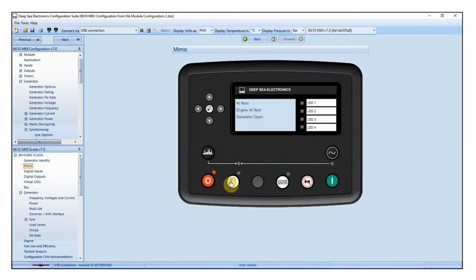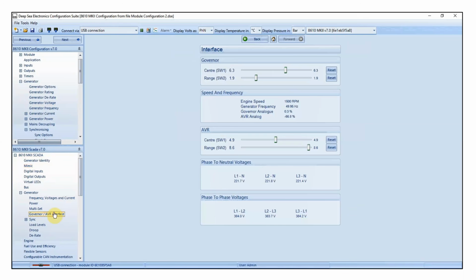And again, we're looking for an AVR output percentage of somewhere between 75 and 85%. Again, remembering that you can only close the generator breaker once the LED underneath the generator symbol has turned on. So we're available, close the breaker, go back to that governor AVR section, and you'll now see that the voltage has started to decrease down to 216, the new setting, and you can see that our AVR analog has resulted somewhere between 75 and 85%. Which is perfect, no problems.